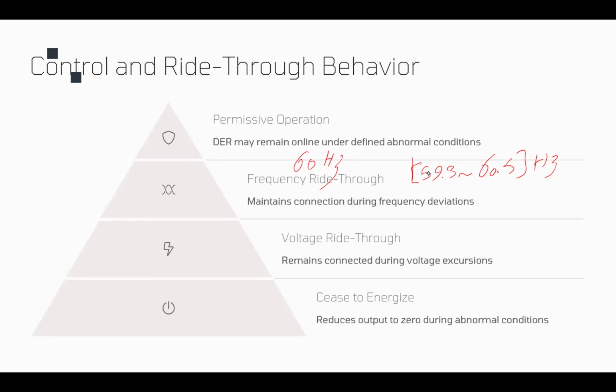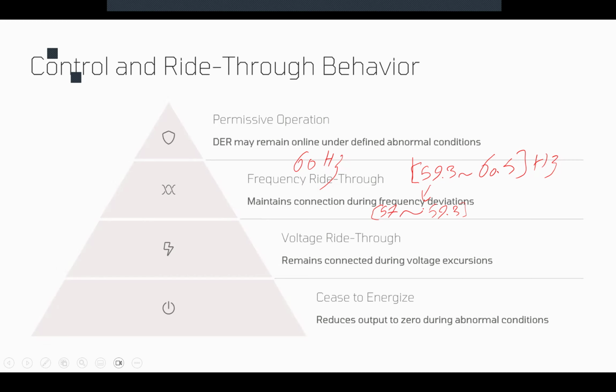Now, if this lower border, the under frequency, happens to go between 57 hertz all the way to 59.3, now the requirement is different, but the IEEE 1547 requires those to stay connected for at least 300 seconds. After that, they could cease to energize or trip in this area. Now, if over frequency exceeds that 60.5 and goes from 60.5 all the way to 62 hertz, again, the DER should stay connected 300 seconds, and after that, they could trip.